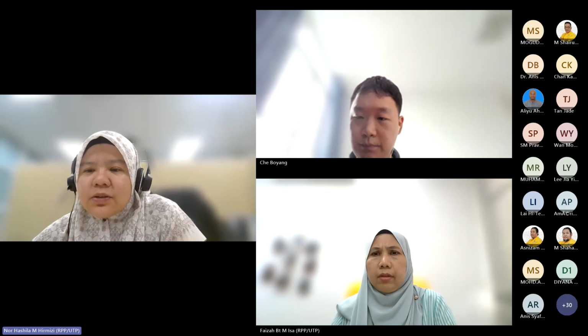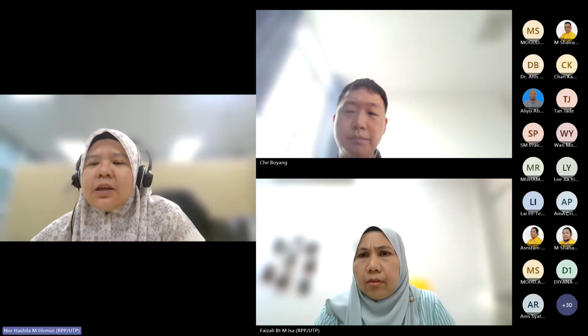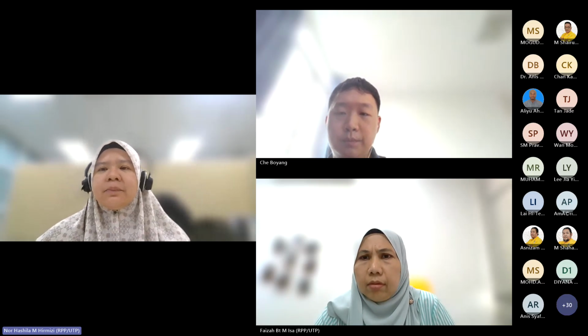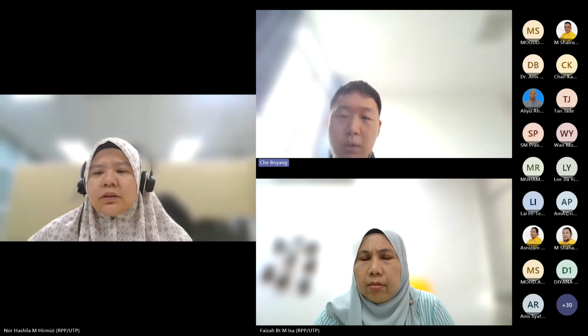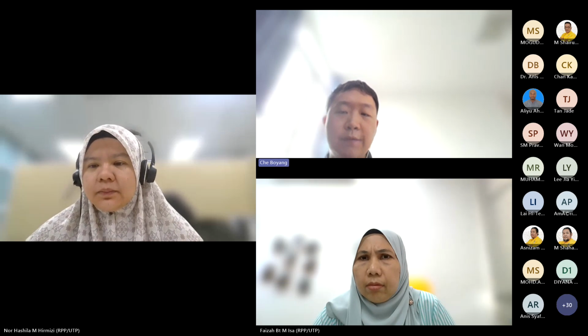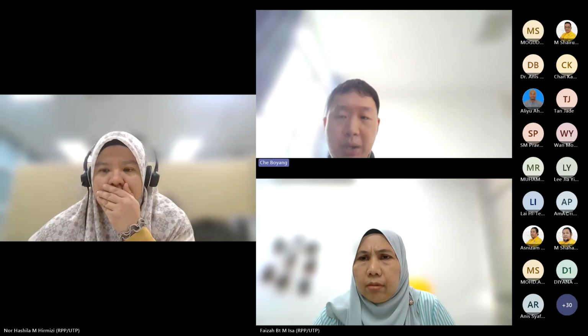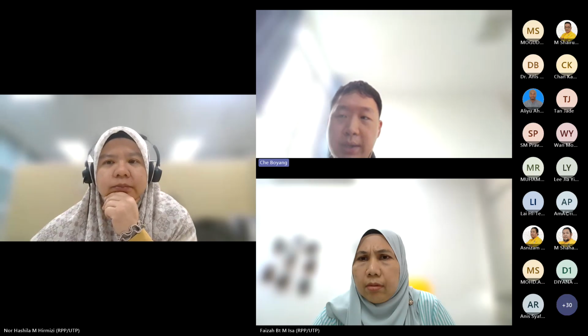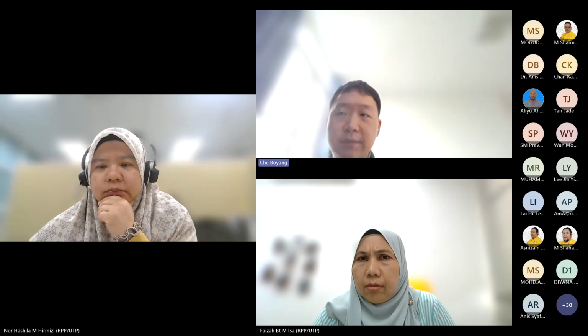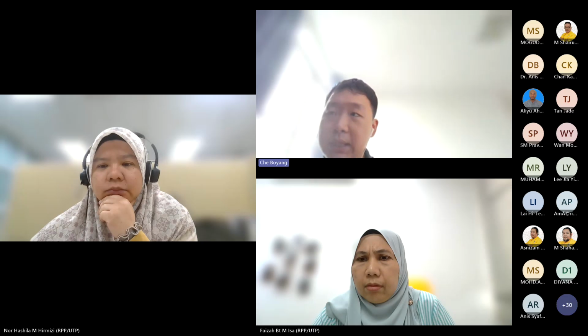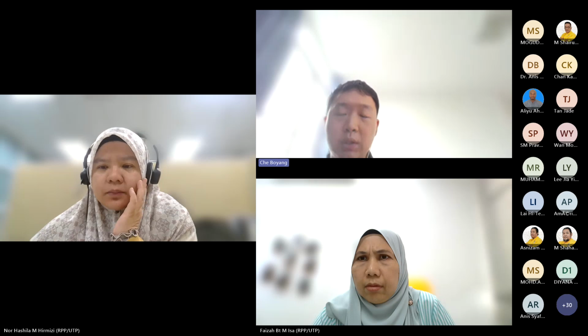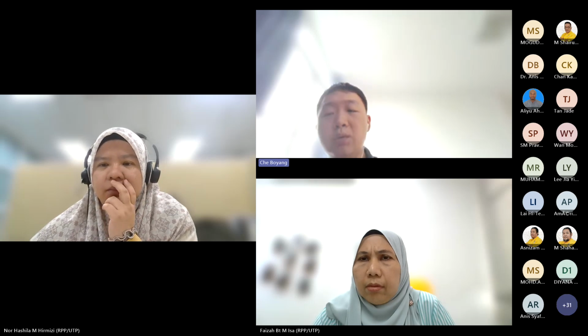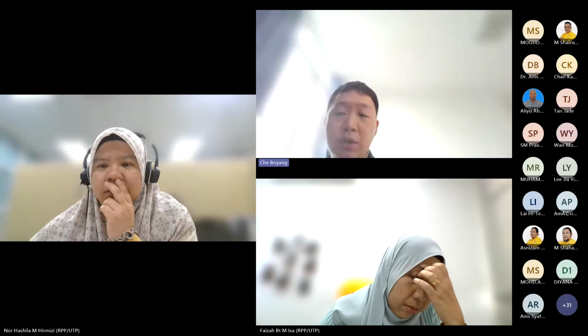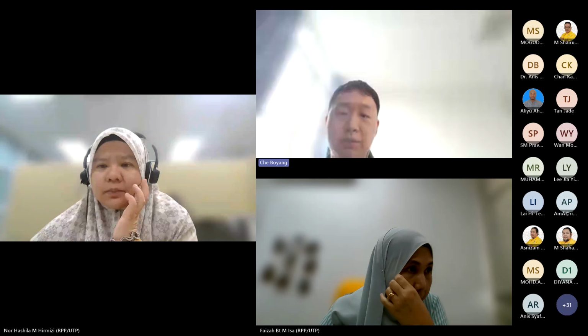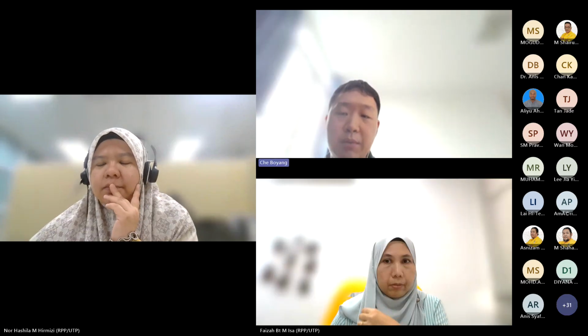Okay. All right. The next one. Hi Dr. Boyang, since you use several filters or mirrors, the laser power will be reduced and not optimized. Is that a disadvantage of the system? Okay, so you are right on this laser power reduction. Once it goes through a filter or a mirror, you will definitely get some loss of laser power. But on our latest model, we use dielectric mirrors, so the efficiency is more than 97%, which means you will have less than 3% loss at every mirror. So overall, at the end of your optical path, when the laser reaches the surface of the sample, you will have at least 50% of your original power. This is already considered good enough for you to get your signal. So that's the nature of the system, I would say.